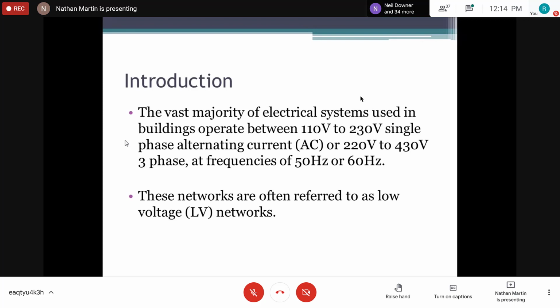If you are the design engineer at your facility, you need to take these considerations in mind: the voltage requirement for the machine, the frequency requirement, and the power requirement of the machine. You'll also look at the physical space and other things, but as it relates to electrical, that's what we'll be looking at. These utilization networks are most of the time classified as low voltage, although we have heavy-duty industry that uses medium voltage. But the majority uses low voltage applications.